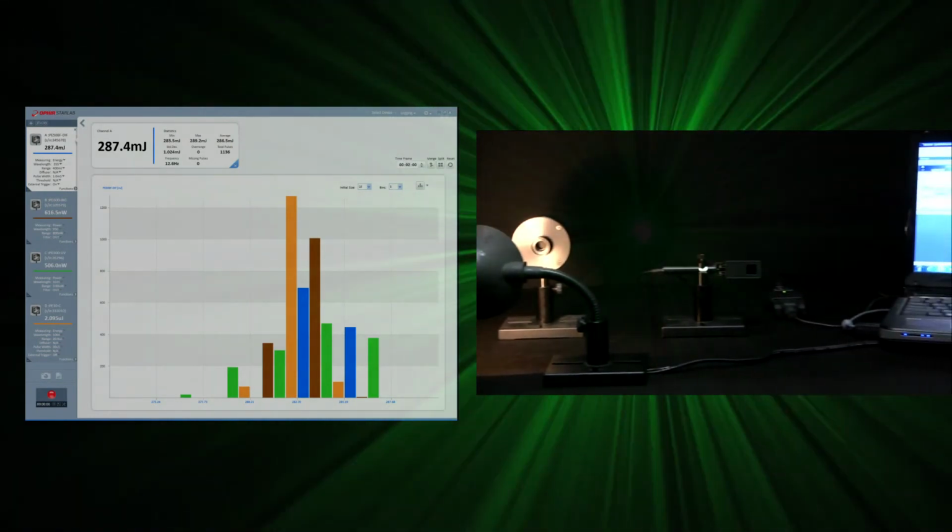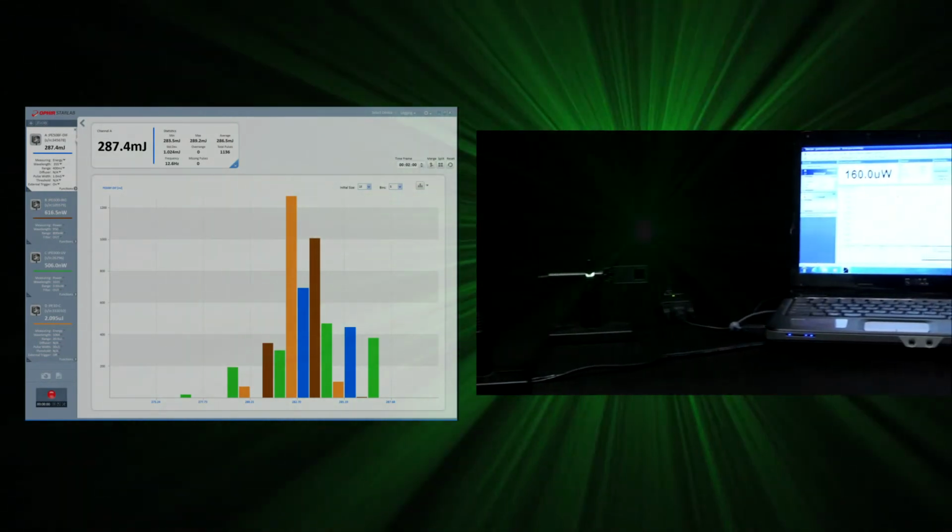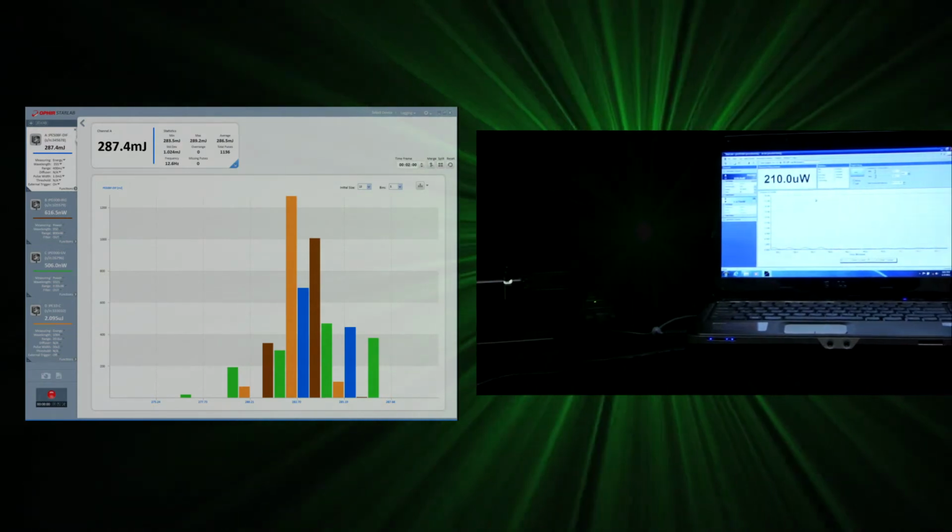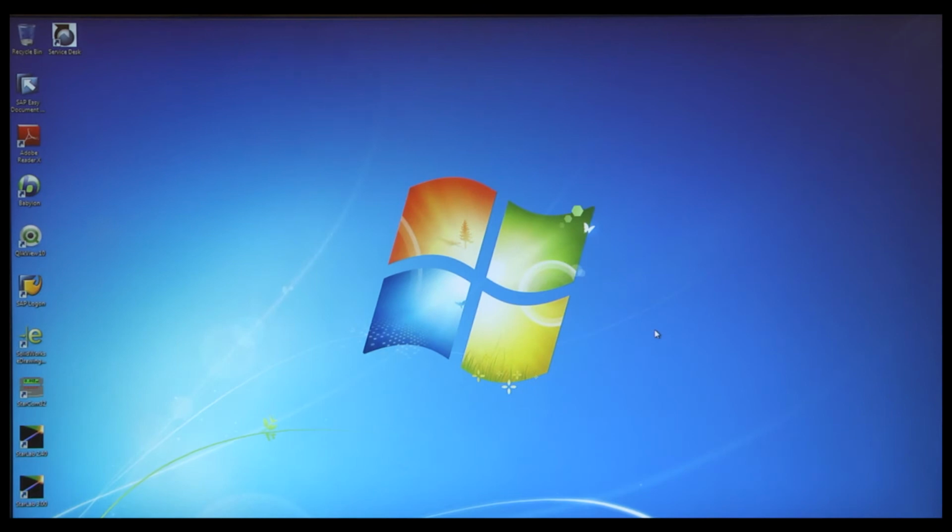The PC software application that's used to communicate with and control the instruments when they're connected to a PC is our StarLab application. StarLab communicates with the instruments via a USB interface, or in the case of the Quasar, a Bluetooth interface. For instruments that connect to a PC via RS-232, one would use the StarCom application instead of StarLab.